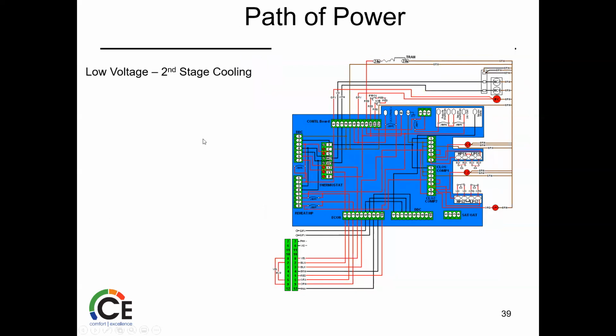So second stage cooling, exact same process, 24 volts to Y2, goes down to the economizer, comes in the yellow wire, goes out in orange. Looks to see if that jumper's cut or not. Do we have a reheat board? Do we have whatever's going on? It's intact.